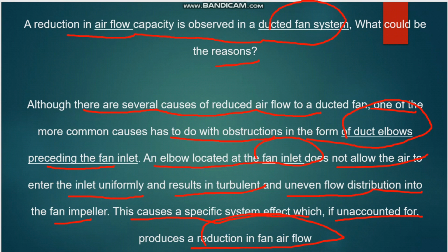So normally, with a ducted fan, we have to see that there is no elbow at a nearby location on the inlet, because we need to avoid turbulence, and so you can make sure that we are getting an even flow distribution into the fan impeller.